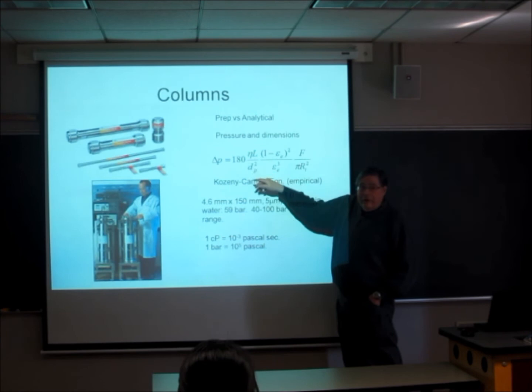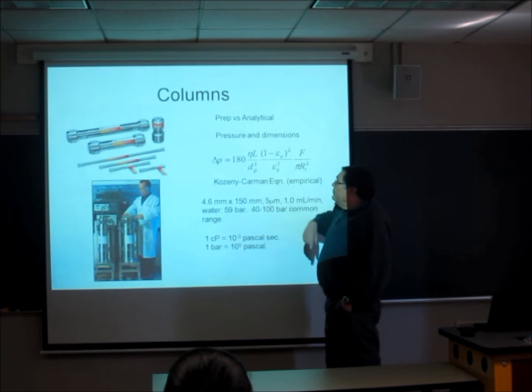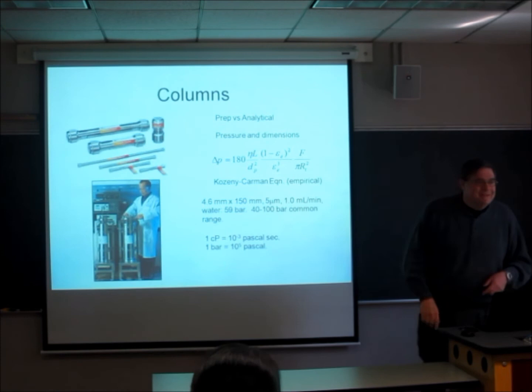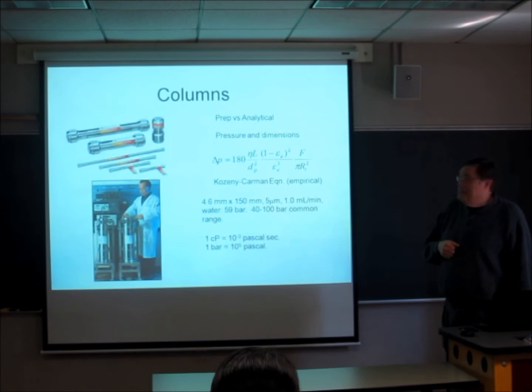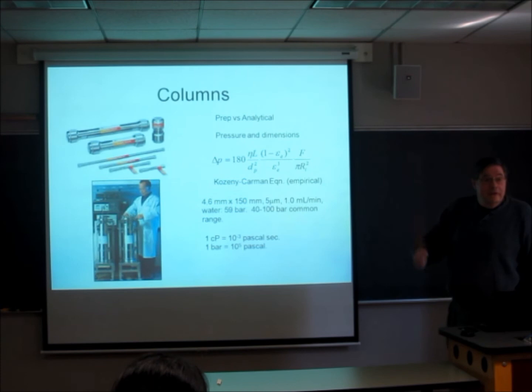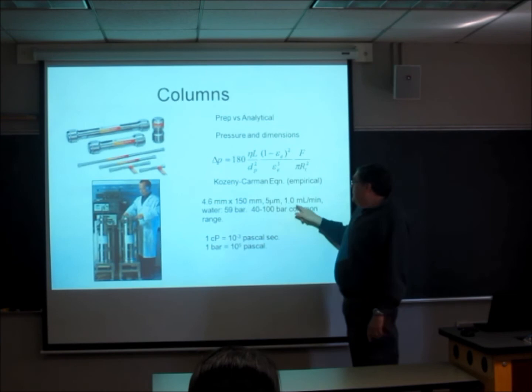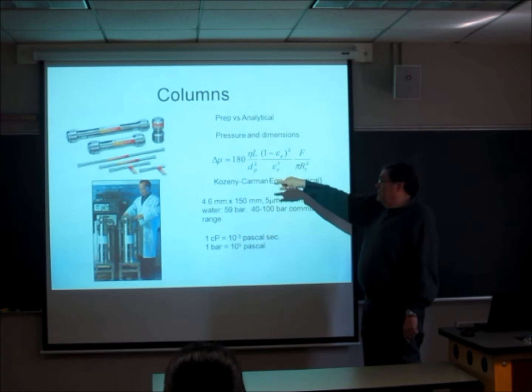Four and a half millimeter inside, 150 millimeter length, five micrometer particles, one mil per minute with water for the viscosity. You'll find a pressure of about 59 bars, 59 essentially atmospheres within a percent of an atmosphere. Commonly, depending on the different solvents, a column like this will show you 40 to 100 bar pressure range. Notice we have length up in the numerator. So if we go from a five centimeter to a 10 centimeter, what's going to happen to the pressure drop? Double. If you go from a five to a 25, you increase the pressure by a factor of five.